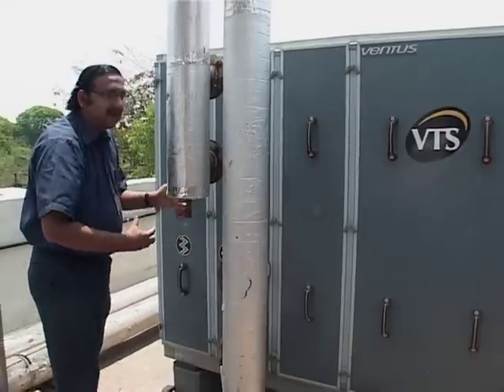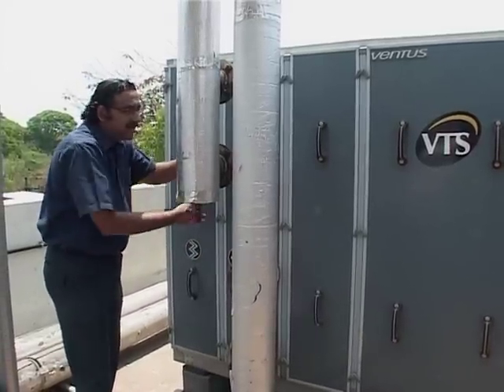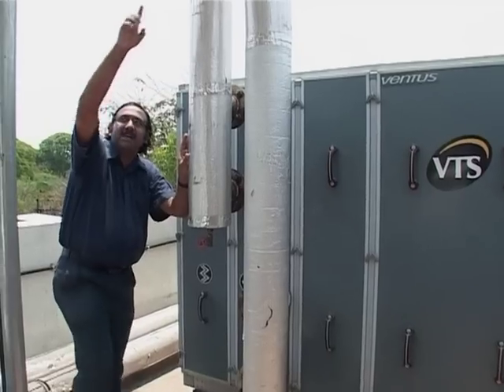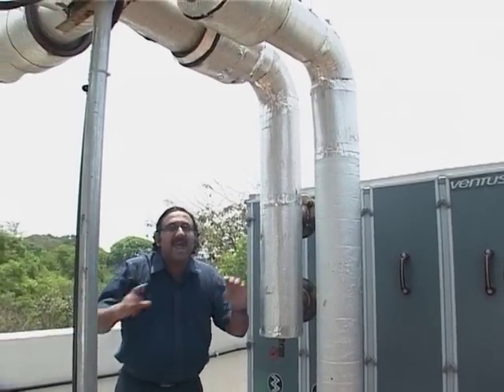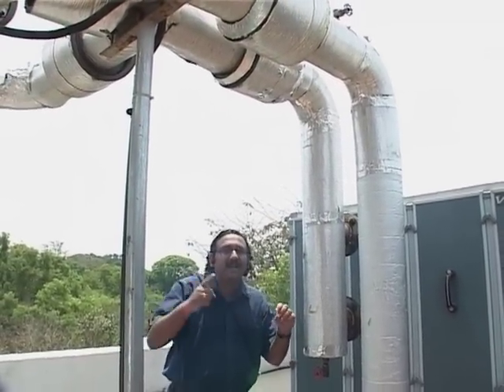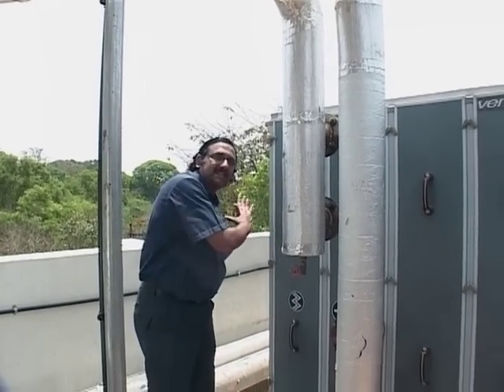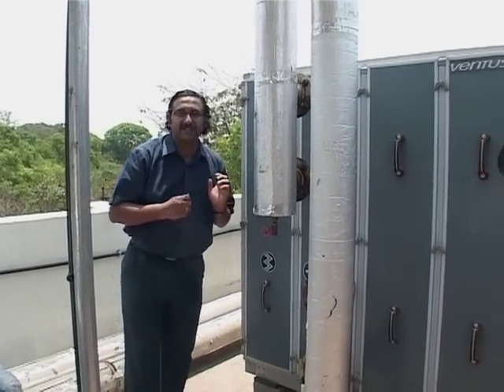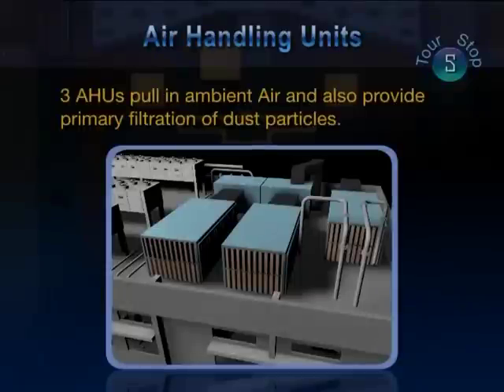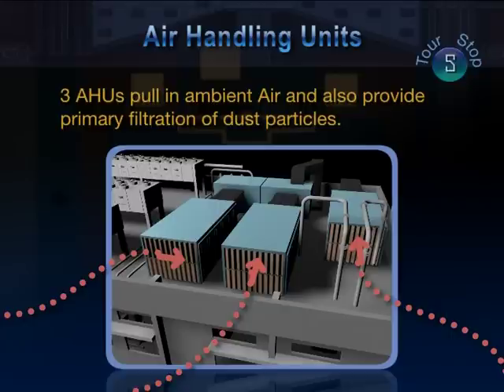And then the remaining chilled water is coming back to these pipes and goes back to the chiller unit. And this water keeps on circulating, thereby cooling the air that is coming into the air handling units. The 3 air handling units pull in ambient air and also provide primary filtration or removal of dust particles before sending the air to the clean room's plenum.